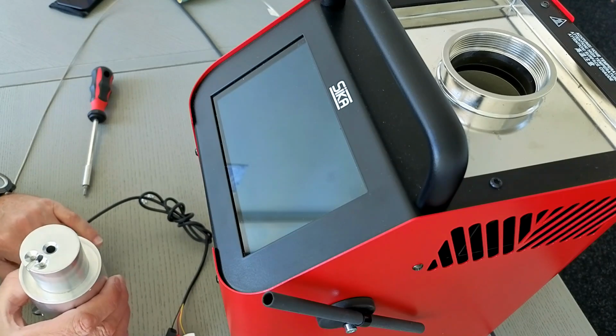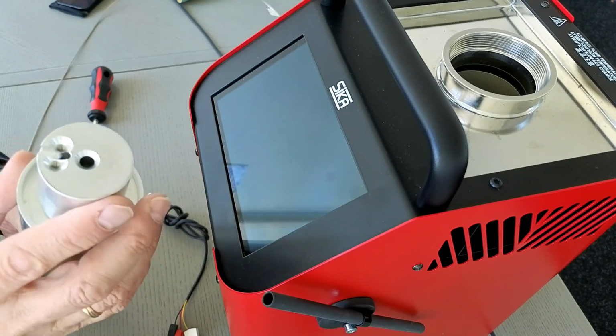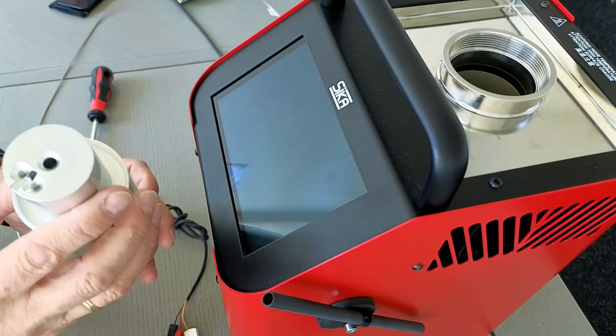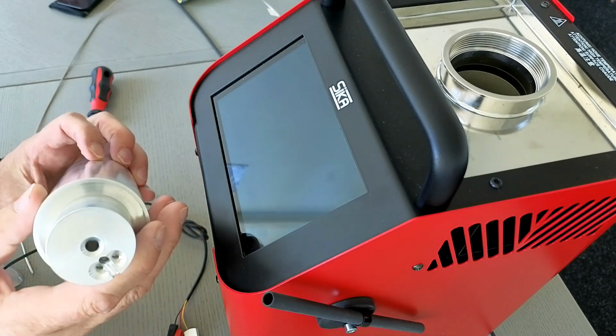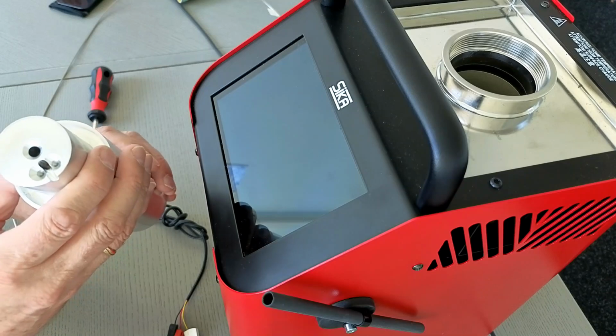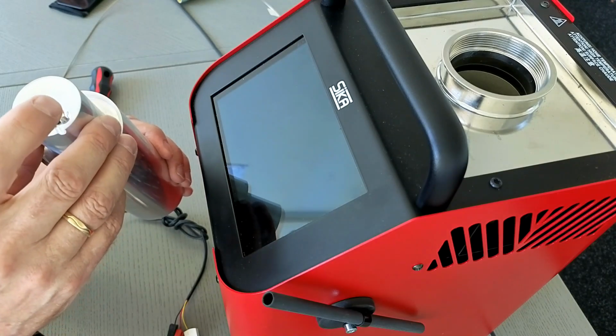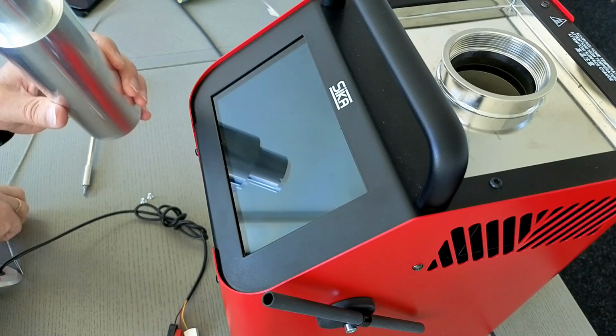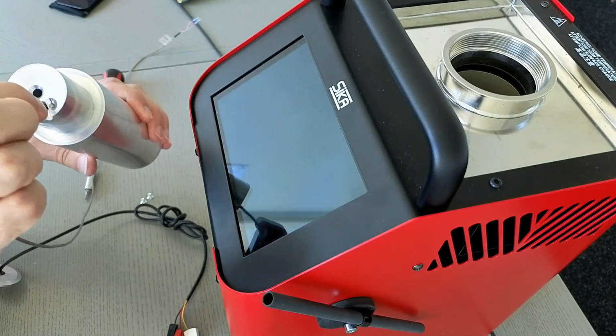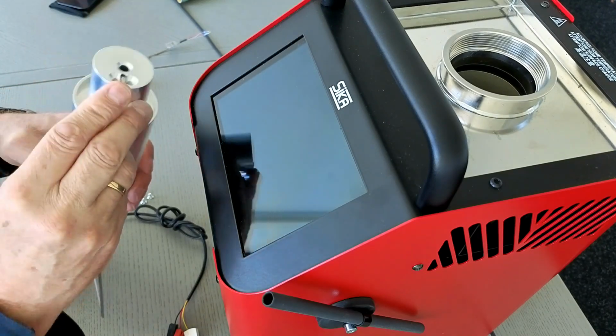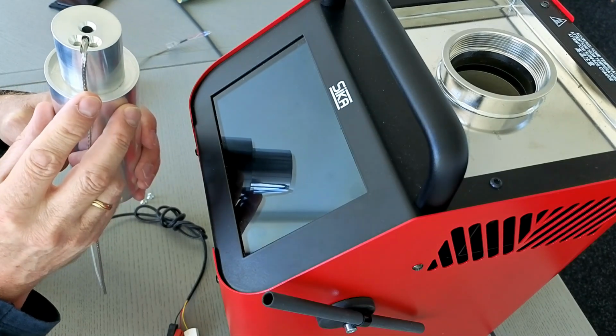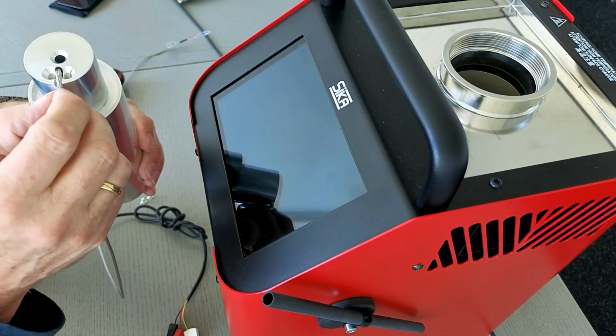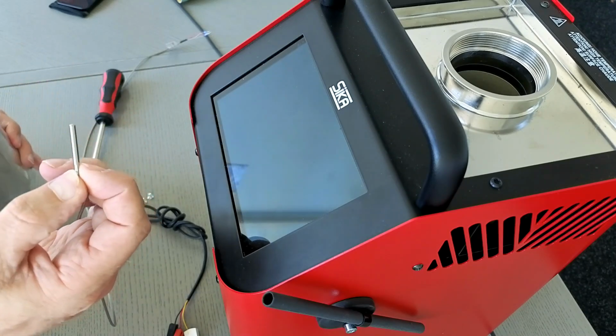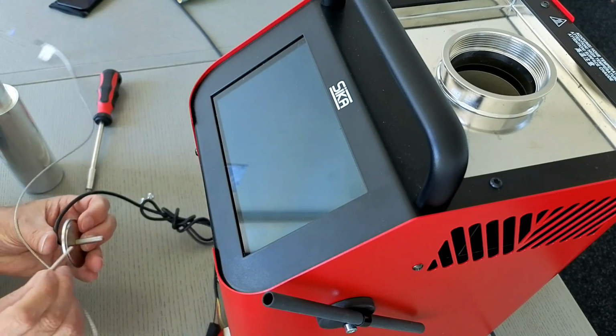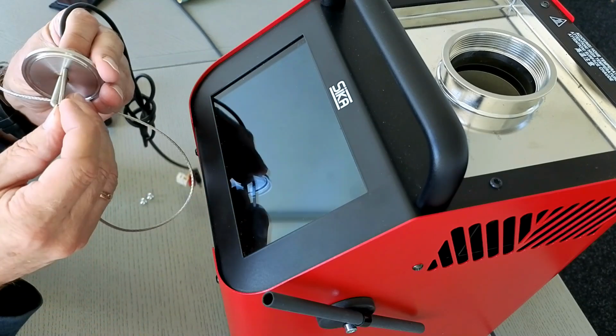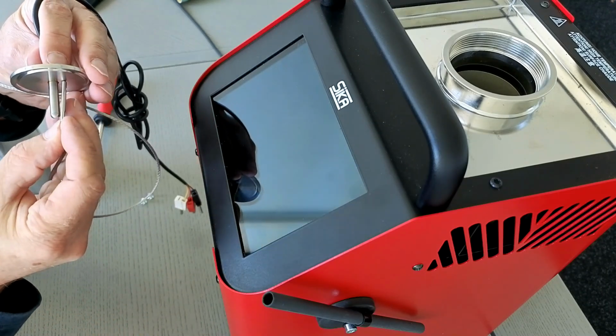By doing this, I use a special insert designed for dry block functionality. You see here a drilling, and into this drilling you can put a reference sensor. It's a cable sensor, so you can move it into position, meaning the length of the reference sensor matches the length of the device under test.